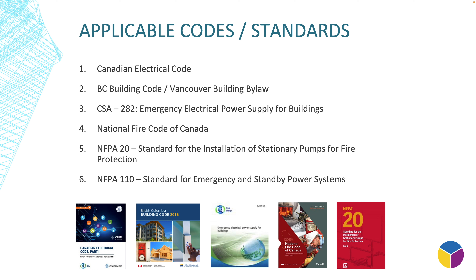The third code we need to follow is CSA 282, Emergency Power System Design for Supply for Buildings. We have this standard — even if we don't have the latest version, the 2015 edition should be good enough for our design. In this standard, they cover how to design a generator, how to design ATS, not only for electrical but also for other disciplines like mechanical — exhaust, air supply, oil supply system, and so on.